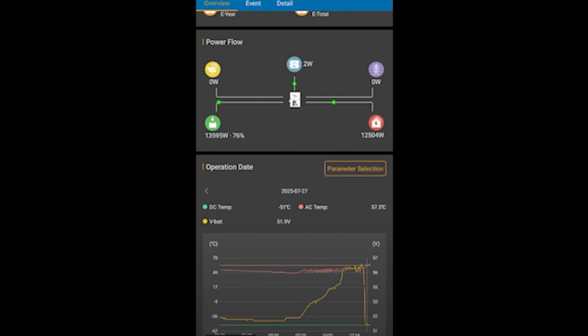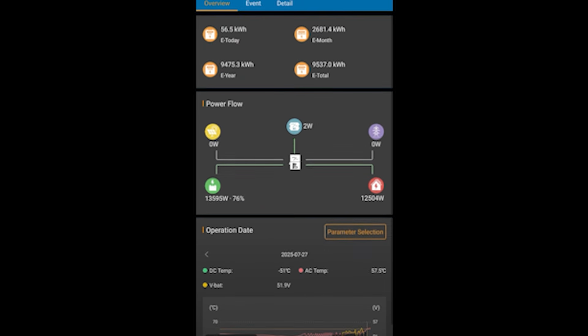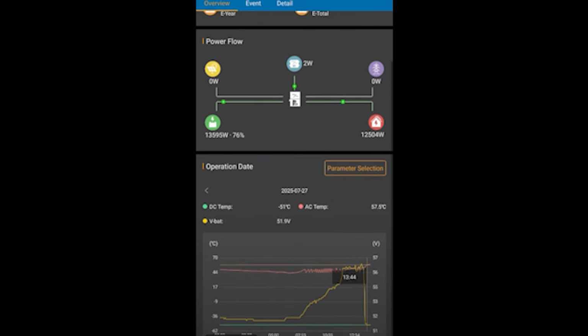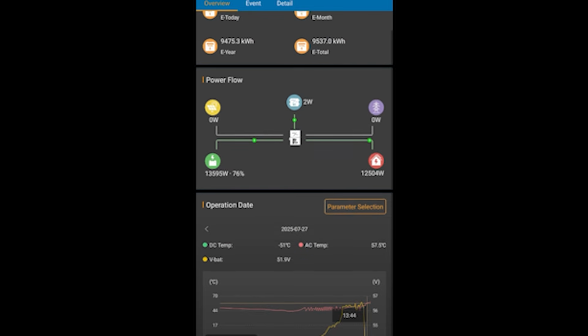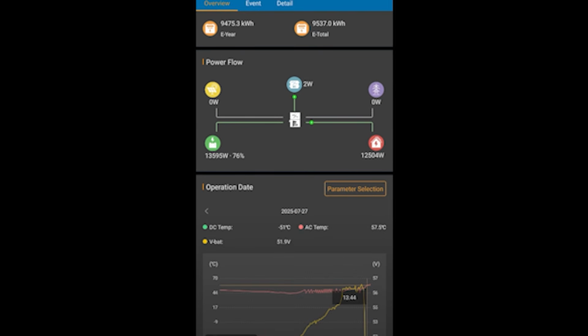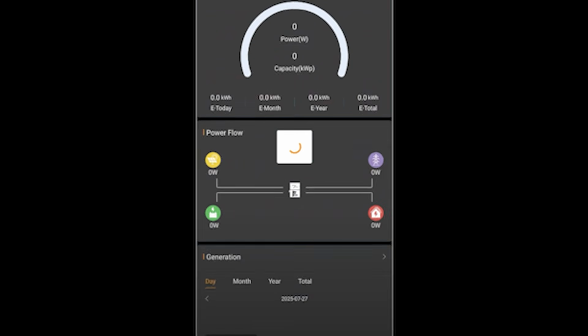Let's see, how long did I run it for? I ran it till I ran out of battery, so it was a constant load. You can see the voltage drops. I pulled some parameters on temperature and voltage, and ran it. You can see there's 13.6 coming out of the battery, 12.5 going back to the grid. I ran it hard until I ran out of battery.